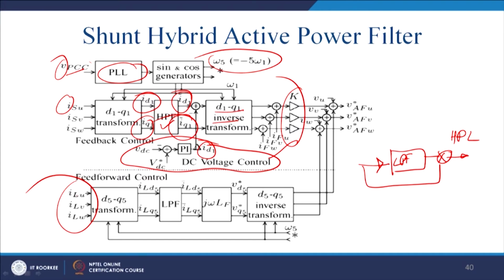And this feed forward will be carried out like this. You will sense the load current, not the source current, of any two of the phases, because you can of course generate the other phase by subtraction with the 0. Then this omega will be fed here, and you will have a dq transformation, but for the omega 5, and thus you get the fifth harmonic component of it. This will be d 5 and q 5, and you feed this component and add up with here.